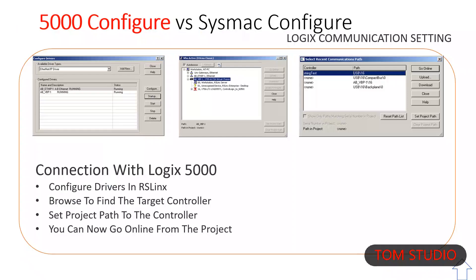In Studio 5000, you configure the drivers in RSLinx, browse to find the target controller, set the project path to the controller, then go online with the PLC.